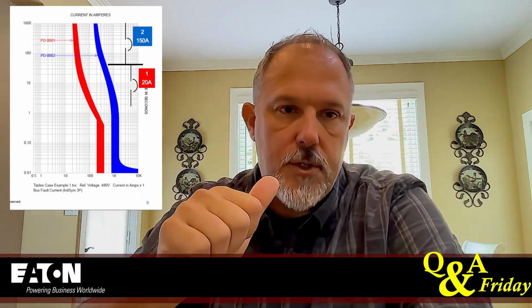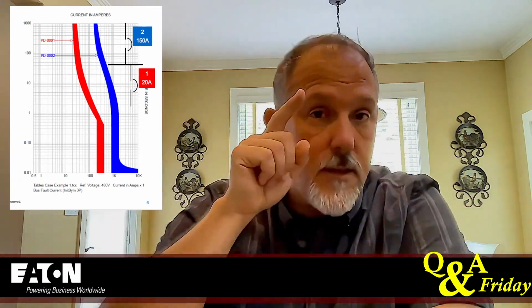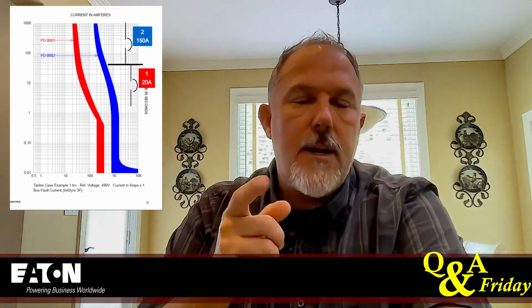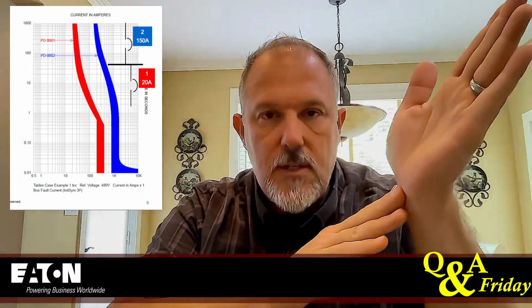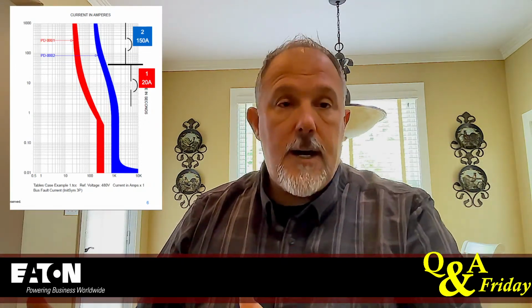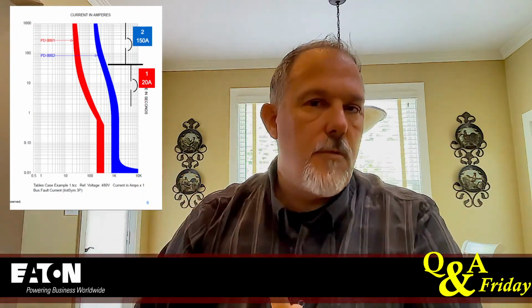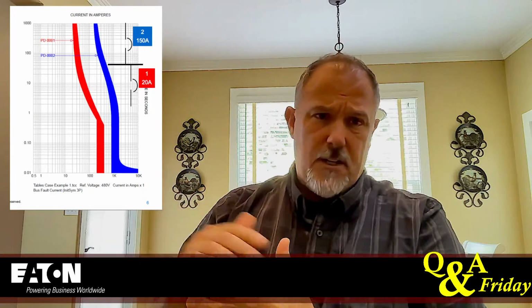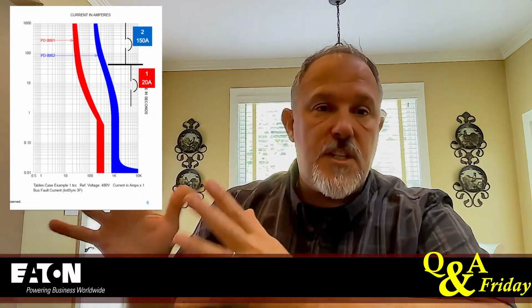So when I looked at the chat off of my YouTube site, here's the message on this. When the fault current gets above 1500 amps for this pair, F150, the breaker, not the truck, BAB20, and I believe it'll go up to a BAB30, when you have those two breakers in series with each other and you run fault current, the moment you get above 1500 amps, they'll both open. Guaranteed. We've proven it in a lab. And this is just, from an Eaton perspective, Siemens, GE, Square D. You put current through those two breakers, similar sized breakers, similar looking curves, they're both going to open above around 1500 amps. And 1500 amps is right in the sweet spot of that blue trip curve, the upstream breaker.